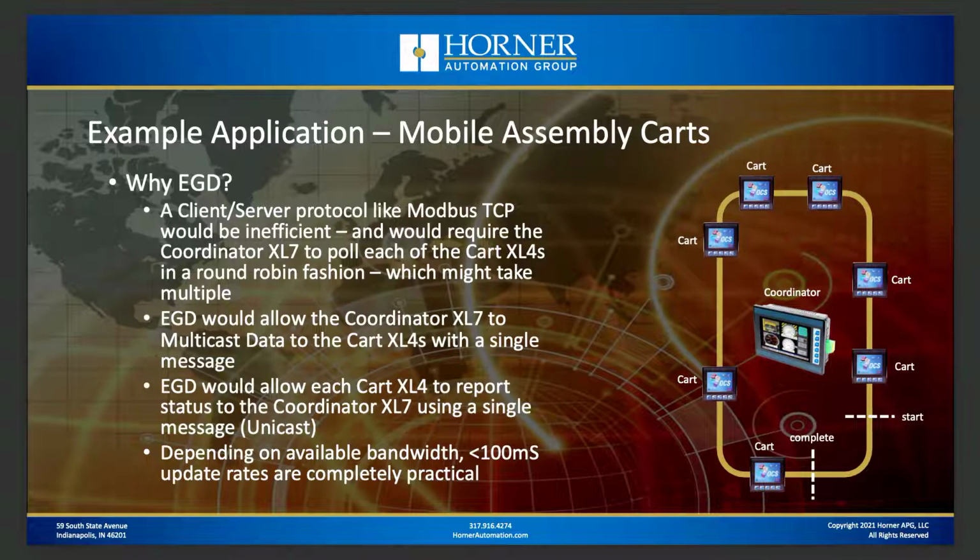So why would we use EGD? Well, because we can overcome that limitation, because this is not a scenario where our messages are on a poll response basis, that you'll see with a lot of client server protocols. Effectively, by using EGD, it would allow the XL7 to send multicast data to the cart XL4s with a single message. In other words, we could send out one big blast of data from the XL7, and that big blast of data could be received by all the carts, more or less at the same time.